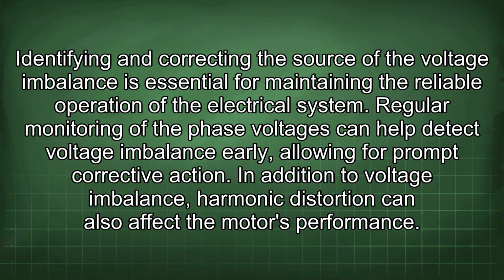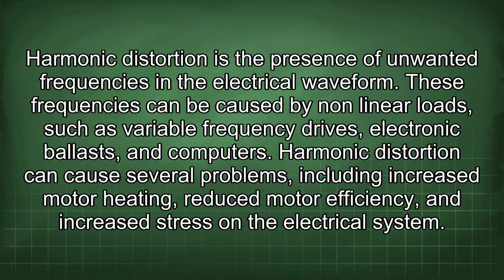In addition to voltage imbalance, harmonic distortion can also affect the motor's performance. Harmonic distortion is the presence of unwanted frequencies in the electrical waveform. These frequencies can be caused by nonlinear loads, such as variable frequency drives, electronic ballasts, and computers. Harmonic distortion can cause several problems, including increased motor heating, reduced motor efficiency, and increased stress on the electrical system.